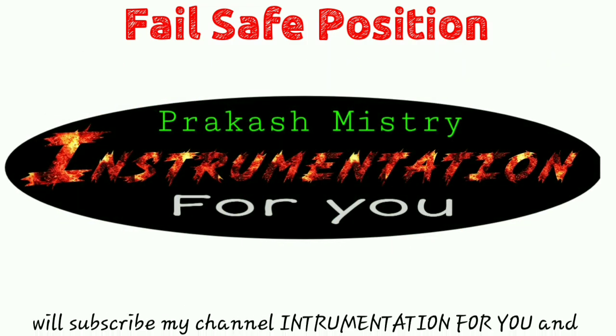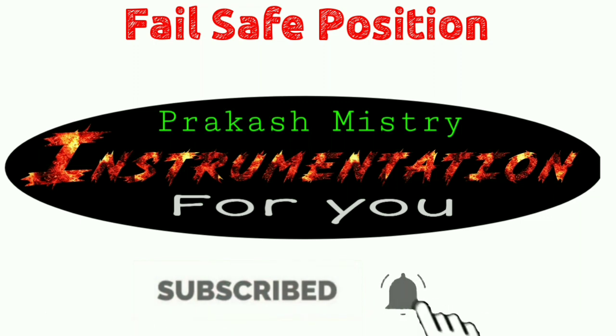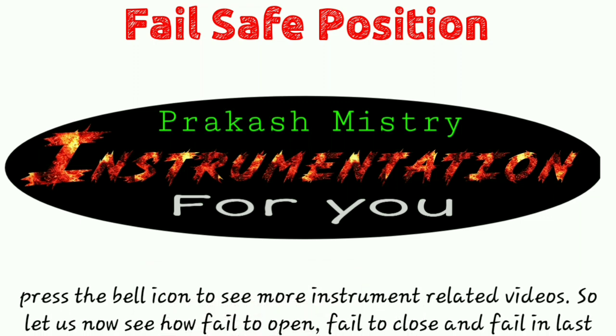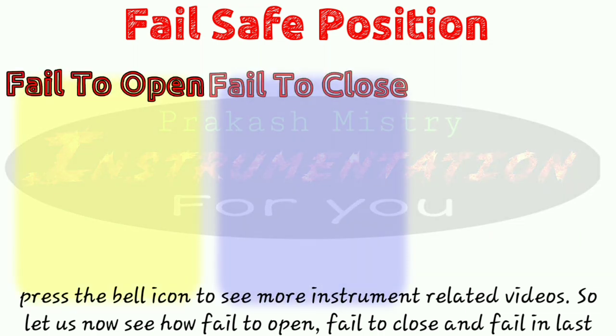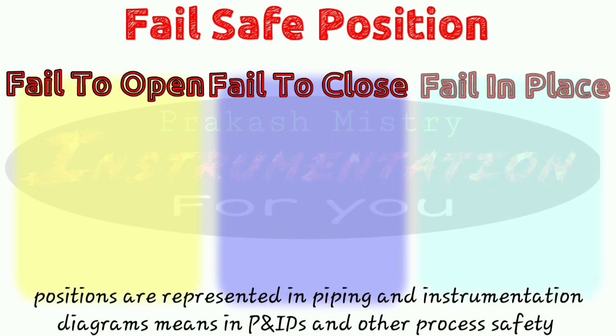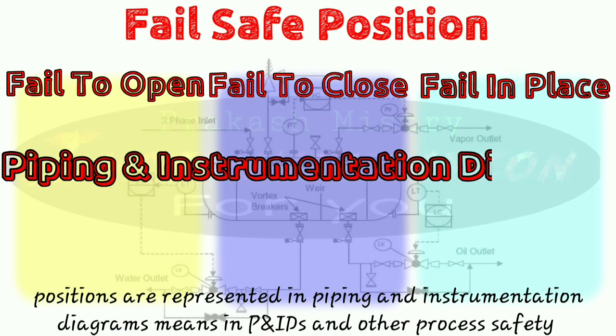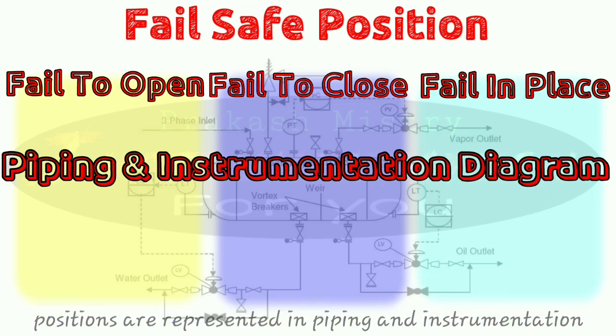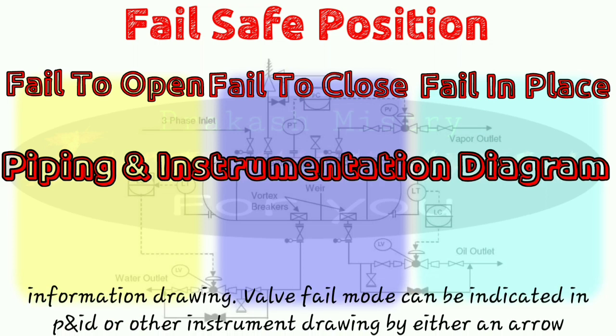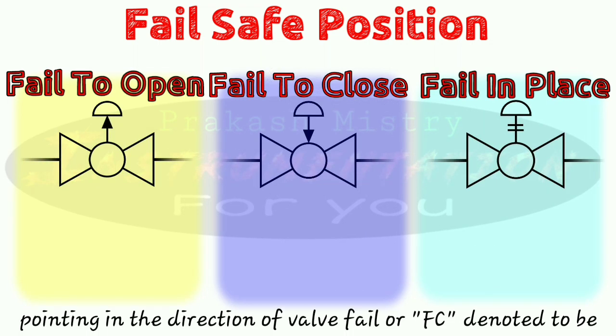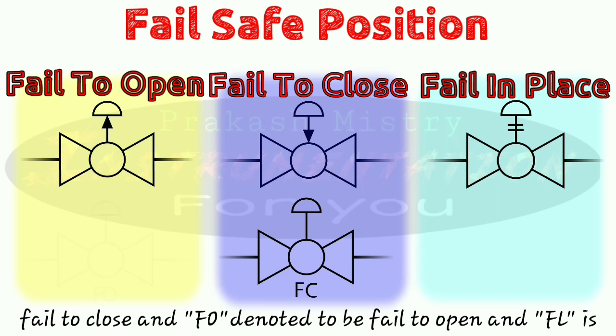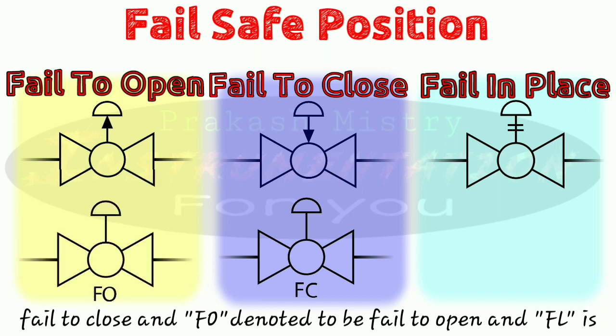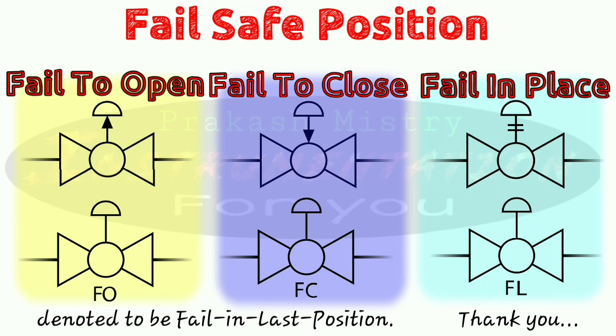Now let us see how fail to open, fail to close, and fail in last position are represented in piping and instrumentation diagrams. In P&ID and other process safety information drawings, the valve fail mode can be indicated by either an arrow pointed in the direction of the valve fail, or by the abbreviations: FC for fail to close, FO for fail to open, and FL for fail in last position.